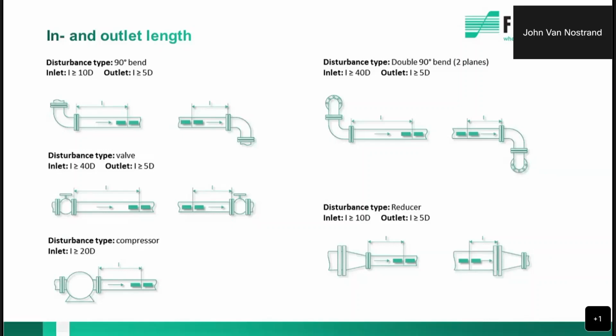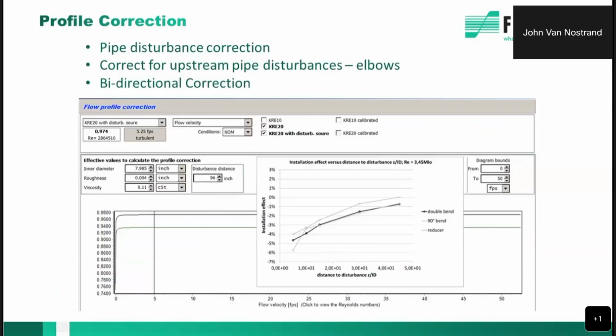And what I mean when I say reflect or direct is whether the transducers are on opposite sides of the pipe measuring directly across, or in reflect, meaning that we're sending the sound wave from one transducer on the same side of the pipe, reflecting off the back wall of the pipe to the downstream transducer that's next to the upstream transducer. I hope that makes sense. But essentially, we're on the same side of the pipe versus opposite sides of the pipe shooting directly across. And when we put them in reflect mount, we can shorten that installation requirement.